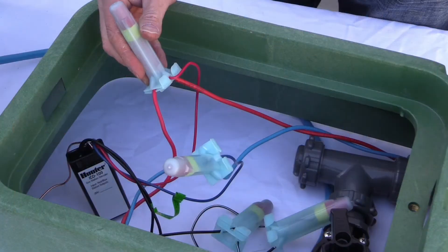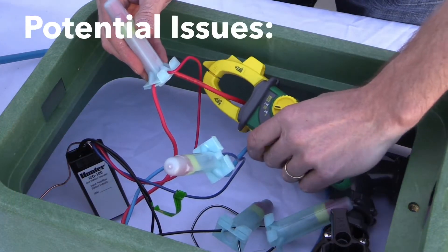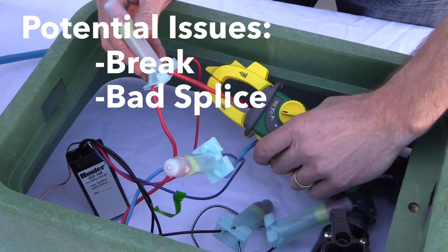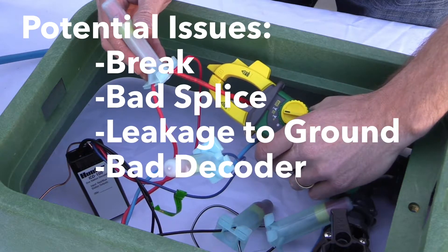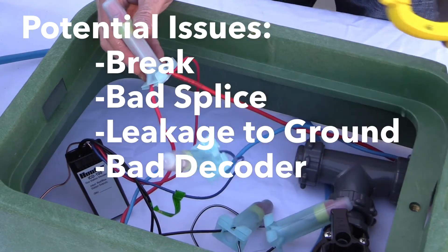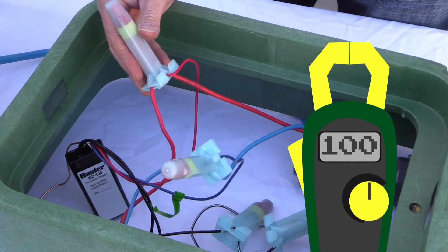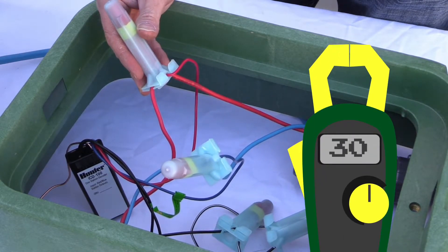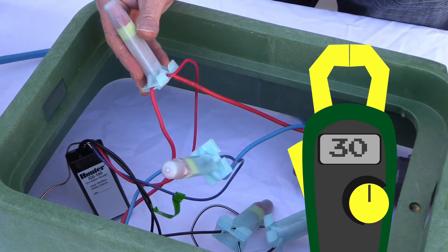If there's a change in this logical progression, you know there's an issue like a break, a bad splice, leakage to ground, or a bad decoder. For example, if your design is meant to draw 100 mA and you read only 30 at the controller, that means 70 of your decoders have been cut off from the system.